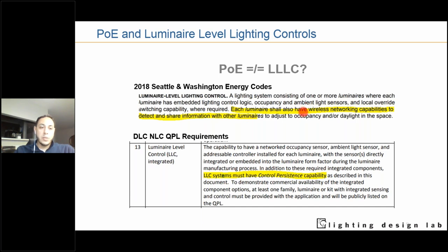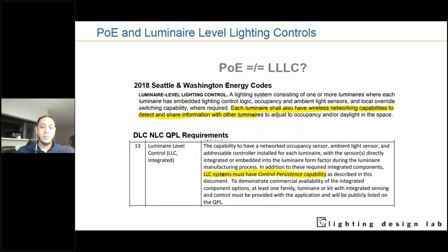And even when we're talking about the DesignLights Consortium, the DLC, a qualifying body that qualifies different products, they tell us that luminaire level lighting control systems must have control persistence. When we were engaging with the DLC, they told us that because PoE lighting does not have control persistence as they define it, they cannot consider it an LLLC solution.